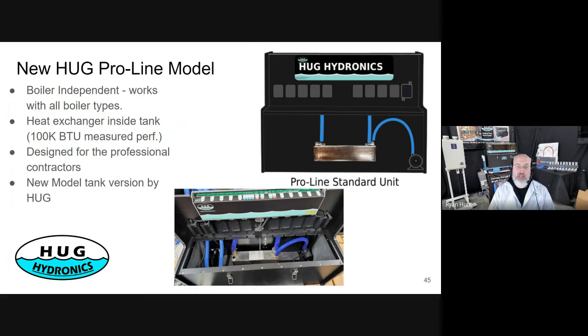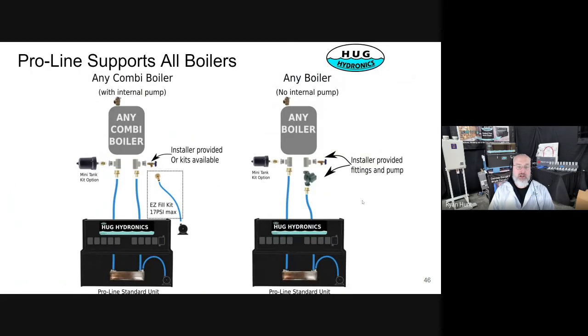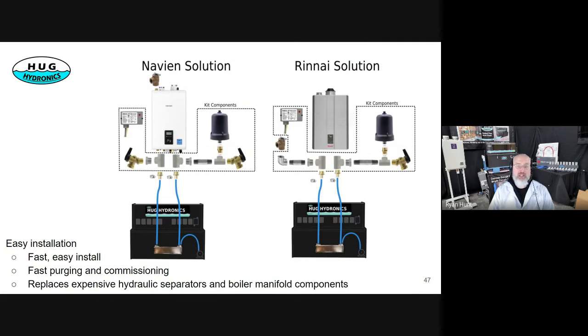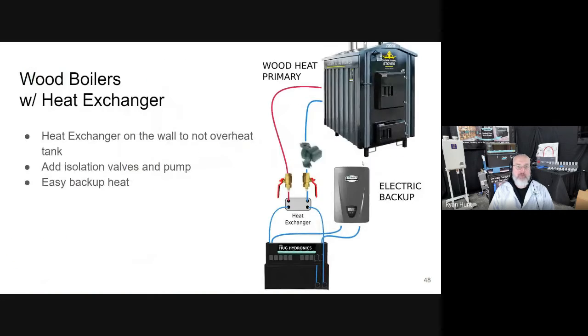To facilitate that, we have a design we call our Pro Line unit because it's usually professionals working with this. And we put a heat exchanger right in the tank, which makes for a nice clean look still, and simple install. Then we have the kit of parts to work with those boilers, particularly with Navien and Rinnai. These are what they will need to adapt. And then wood boilers are another popular option. On those ones, you want to take the heat exchanger out of the tank and keep it on the wall because there's always hot water flowing through there, and we don't want to overheat the tank.